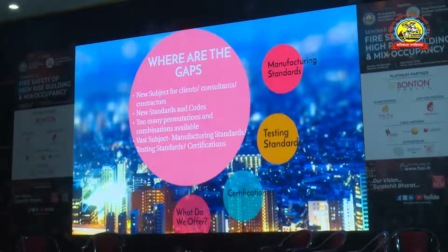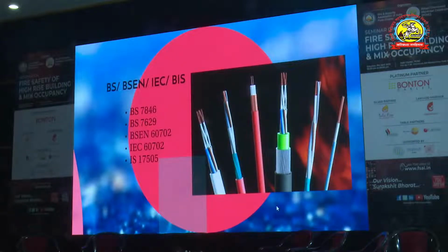Going further: BS 7846 is for armored cables. BS 7629 is for unarmored fire survival cables. BS EN 60702 is for copper tubed fire survival cables, the most expensive and safest, but only required in highly flammable situations like nuclear power plants and oil refineries. IEC 60702 is the same kind of cable. And lastly, IS 17505, a replica of BS 7846, is for armored fire survival cables, which is mostly used in the Indian industry right now.